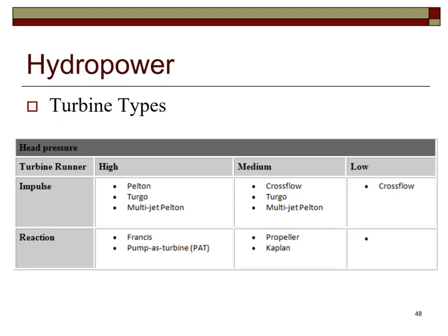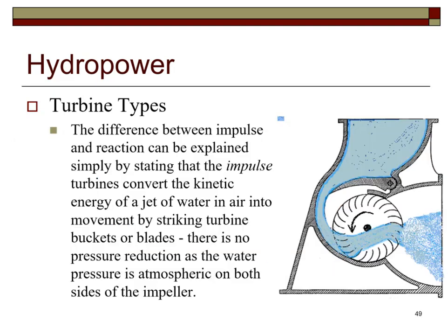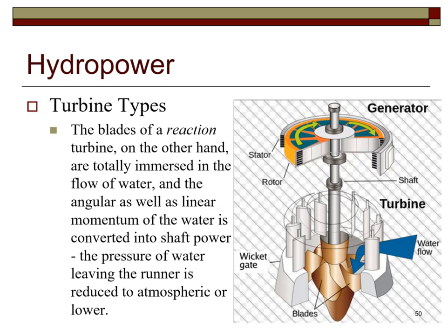The types of turbine and whether they operate on high, medium, or low pressure are presented in tabular form. Simply stated, an impulse turbine converts the kinetic energy of a jet of water in air into movement by striking turbine blades, with no pressure reduction since water pressure is atmospheric on both sides of the impeller. The blades of a reaction turbine are totally immersed in the flow, and both angular and linear momentum of the water are converted into shaft power, with the pressure leaving the runner reduced to atmospheric or lower.